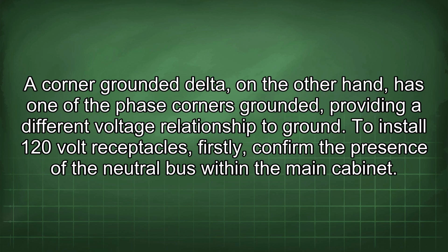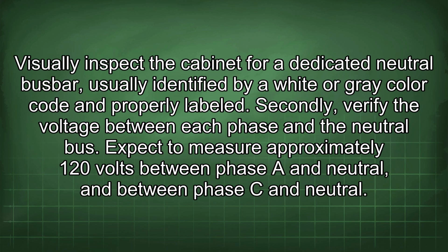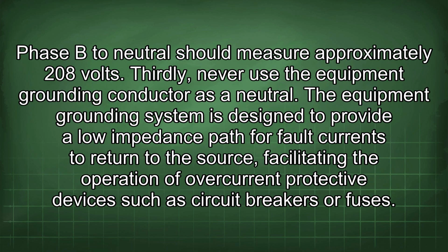To install 120 volt receptacles, firstly confirm the presence of the neutral bus within the main cabinet. Visually inspect the cabinet for a dedicated neutral bus bar, usually identified by a white or grey color code and properly labeled. Secondly, verify the voltage between each phase and the neutral bus. Expect to measure approximately 120 volts between phase A and neutral, and between phase C and neutral. Phase B to neutral should measure approximately 208 volts.